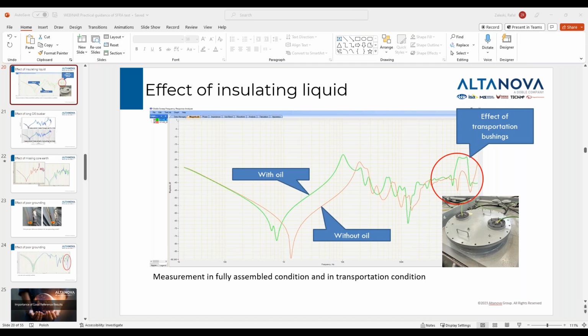Okay, should the SFRA test fail, what are other tests you can perform to prove that the failed test result is true? Can the ratio and DC winding resistance test help for further analysis? Well, that depends on the case. If this is severe damage in the transformer, like everything mashed inside, surely a ratio test would show this, or magnetizing current quite often shows you that something is wrong inside, and the SFRA will also show it. In cases like some of the ones which I presented today, it is not that easy to find another test which will support your findings from SFRA. So this is always a case by case situation.